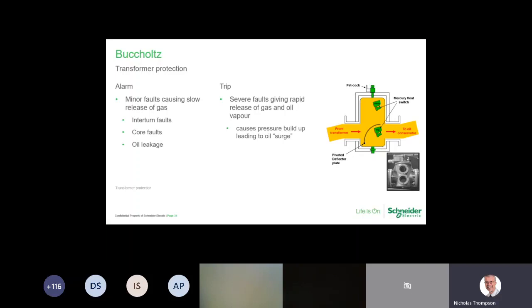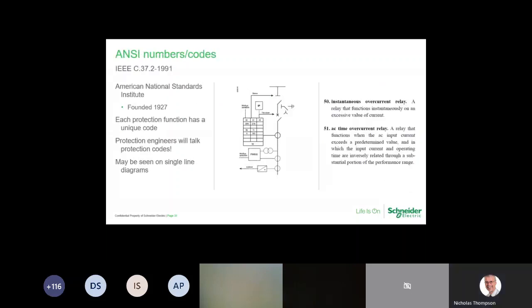Whether they actually use mercury now in the modern ones, I can't comment on that, but you will find it will have windows in there so you can see whether you've got sufficient oil in the Buchholz, and it will be part of the transformer construction with a terminal box and then wired out to the appropriate point on the relay. And bear in mind that the protection relay may be a little distance away from the actual transformer in the compound.